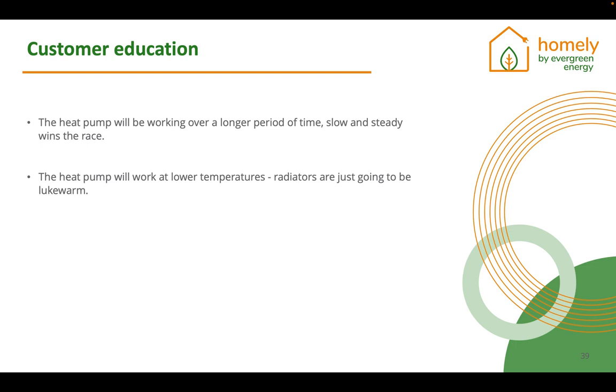You also need to let the customer know the radiators will feel cool to the touch whenever the outside temperatures are warmer, because the heat pump might be running at a 35, 30-degree flow temperature, which if you touch the radiators, they're actually going to seem cool. That is, again, Homely doing the right thing by maintaining the indoor temperatures that the customer has requested with the lowest flow temperatures possible. So maximizing the efficiencies and maximizing the comfort whilst minimizing the cost of running the heat pump.